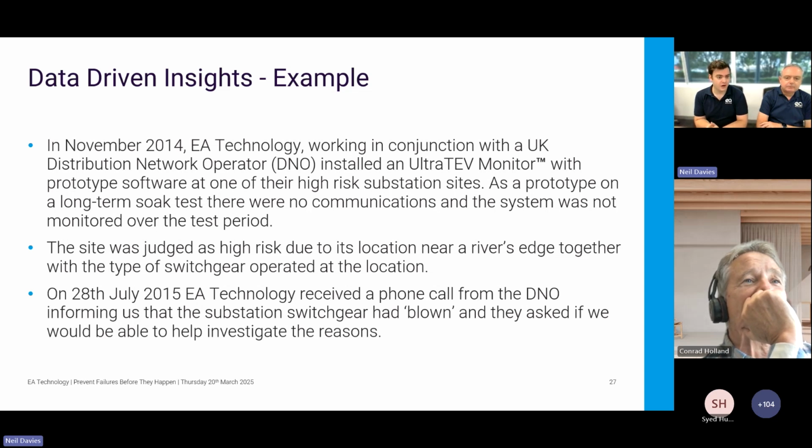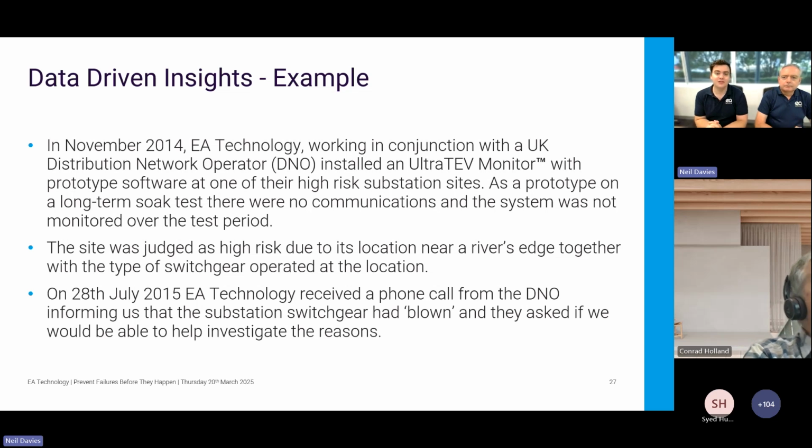So that was identified. They did a lot of work to know that, but they also had a population of those assets to manage. So they went through and identified assets that were at high risk. That's where this particular case scenario comes from. It comes from one of their substations that was right on a river's edge, quite a critical board, and due to its location had a naturally quite high humidity. They got into contact with us. We installed a monitoring system so it would be alarmed and they could catch any of those problems.